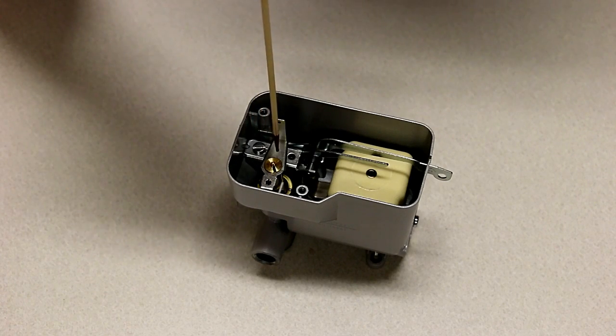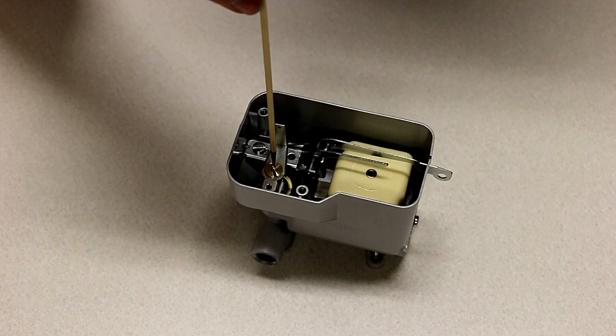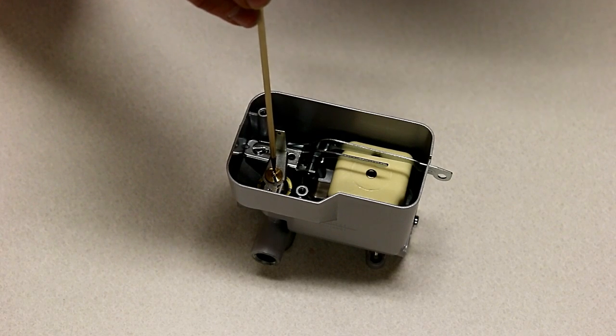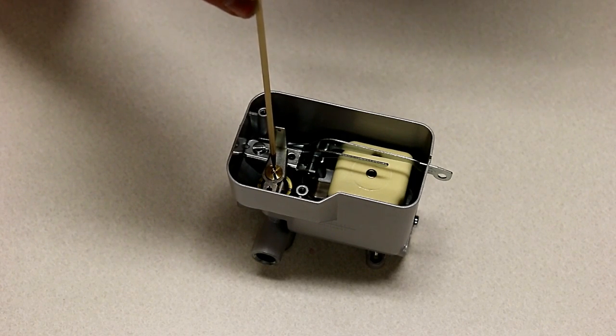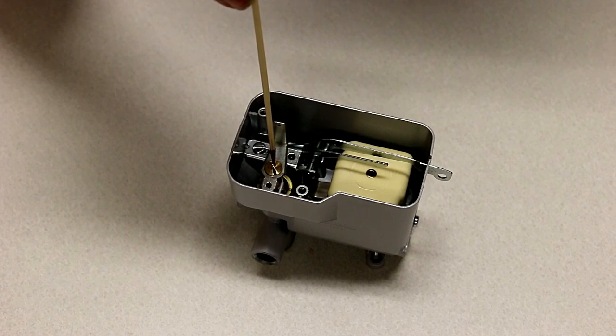When you turn the dial towards low, it pushes down on this and eventually will stop oil completely. When you rotate the dial towards high, it allows the metering stem to come up and delivers more oil to the burn pot.